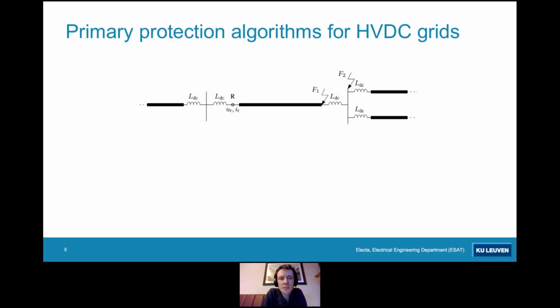Next, we need primary protection algorithms for these HVDC grids. That means that we need to detect and identify faults in the millisecond time range by using the voltage and the current measured at one line end. And we need to discriminate faults on the line from faults external to that line. So fault F1 is an internal fault, which we need to discriminate from fault F2.